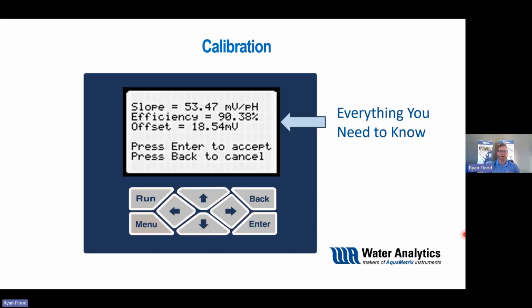So in terms of efficiency, about 78% and below is really where you want to start looking at from a maintenance standpoint of maybe replacing the salt bridge or the reference solution, performing some of that cleaning. Anything above that, you're going to be getting good readings. And it really comes down to what's the level of accuracy you want to be getting and the level of resolution you want to be getting across the range that you're measuring.